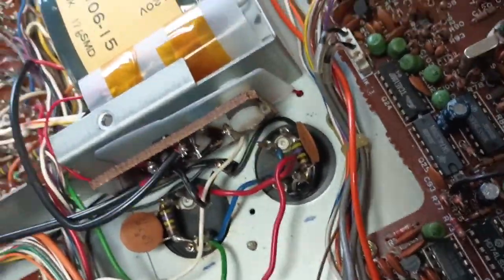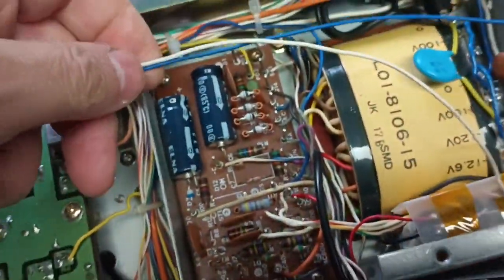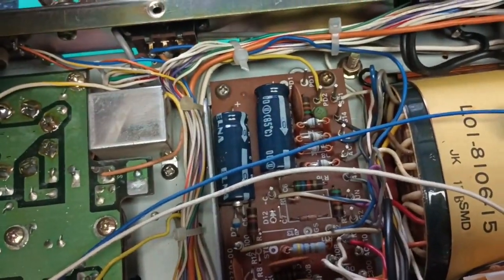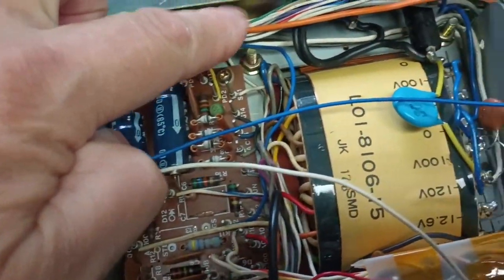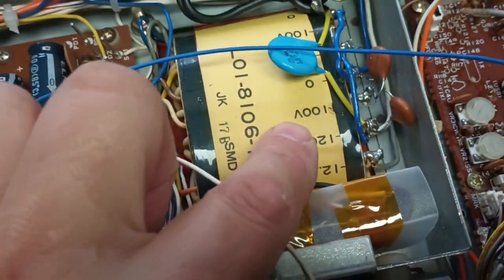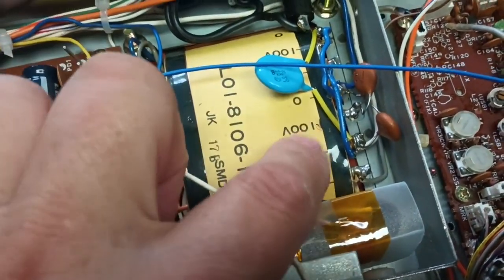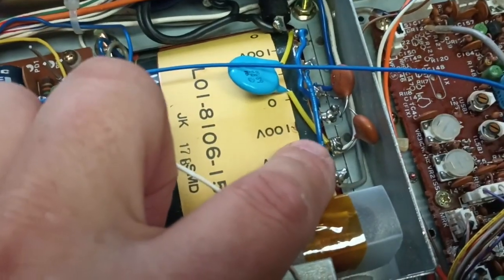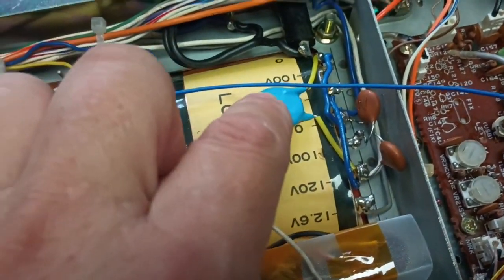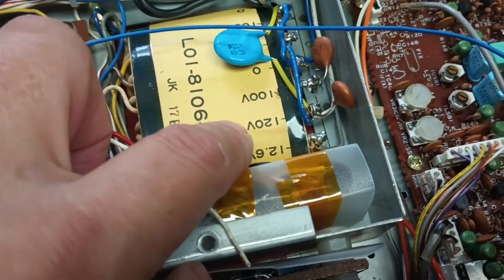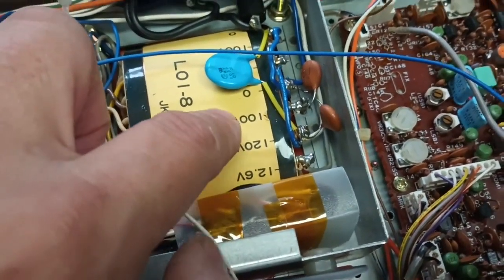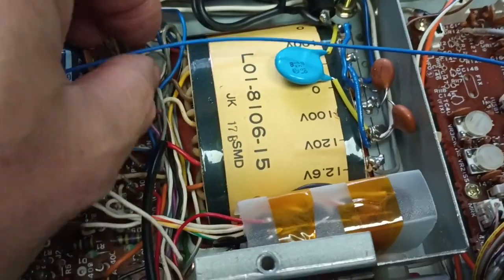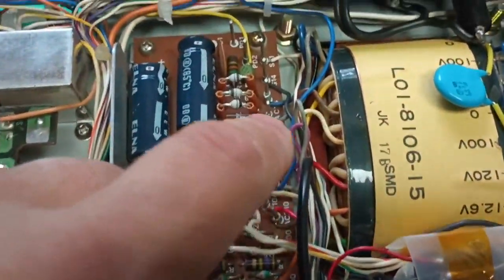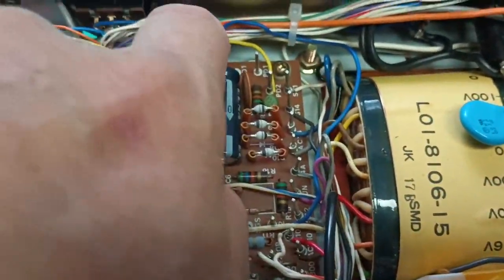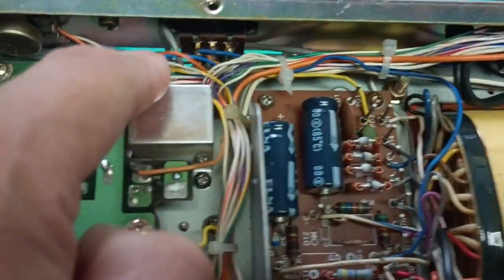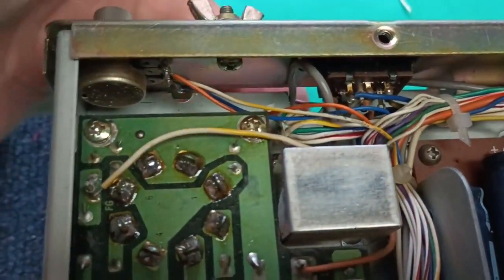For the fan wires, use the original blue and white wires that came from the original fan up through here along this bundle, and they originally went to the 100 volt taps on the transformer. So just cut those blue and white wires off, make sure you cut the right ones, and while you're at it, make sure and check to see that the transformer's bridged for 120 volts and not 240. So reuse those wires and route them along here and under the screen grid switch and right up through that little cutout there. That's the one that goes up in the final compartment.